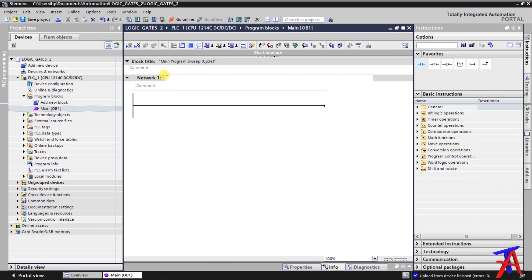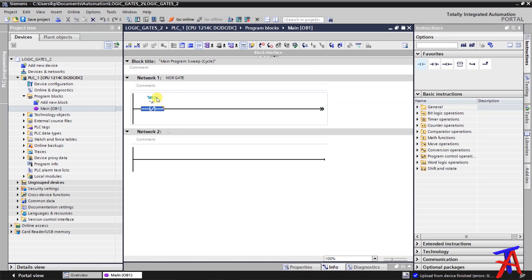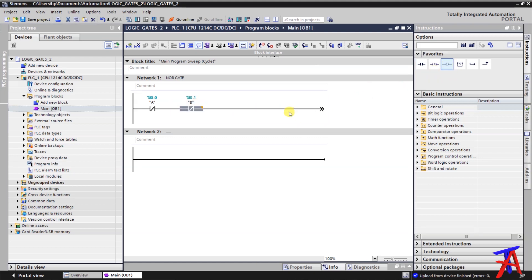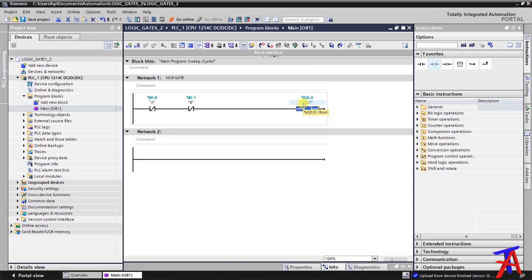So let's make the logic for the NOR gate. We will add an NC button for input A, and another NC button in series for input B, and the output coil. So as we discussed, the formula of the NOR gate is a plus b whole complement, or a-bar dot b-bar, and this is how we make the logic.